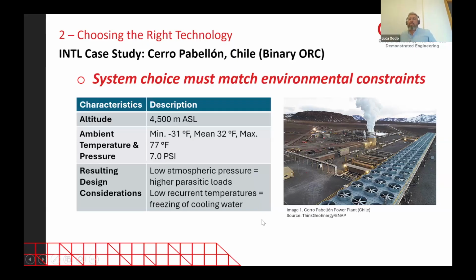360 days per year. If I remember well, there were also some collateral issues that led to the choice of the binary system, and there are three units installed in the area of Cerro Pabellón. One issue was that even for civil works, foundations for huge steam turbines were not constructable because the concrete would not dry in sufficient time due to the environmental conditions. That was a huge issue that led to the selection of smaller units, such as the binary ones. Another point was that the plant had to be automated because nobody could live at that altitude due to Chilean regulation. So I think that's a good example.